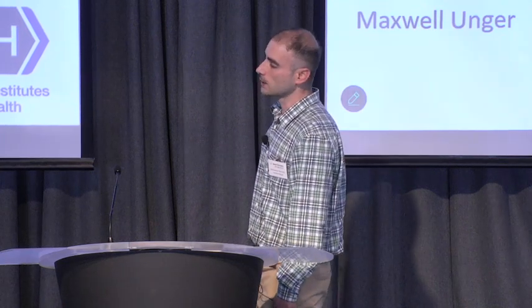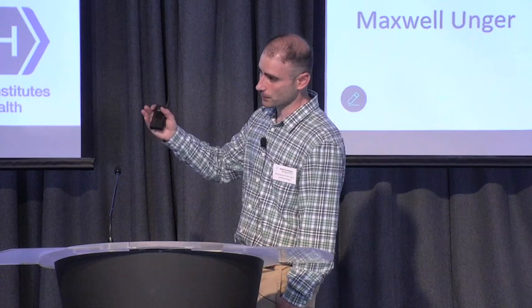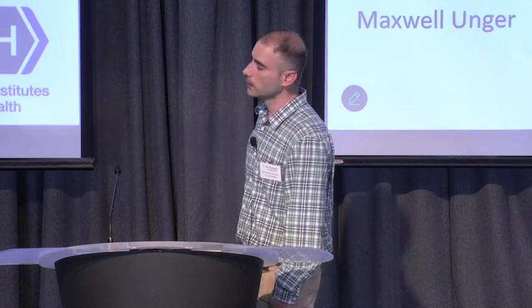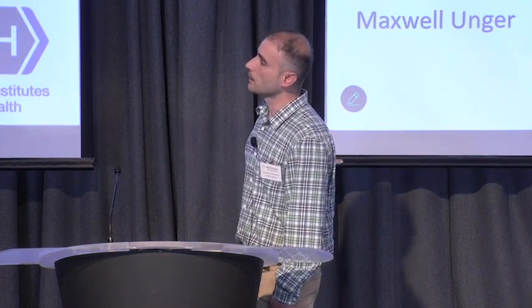It's quantitated at the millimeter scale. The faster you go, the variation increases a little bit, but this doesn't prevent us from picking the colonies because the rows at which we print are 5 millimeters apart. The largest variation that I've seen is about 1.5 millimeters. So I understand that there is some variation and it's not a perfectly straight line, and there might be various sources of error contributing to that.